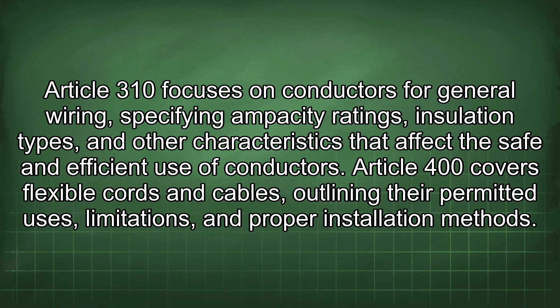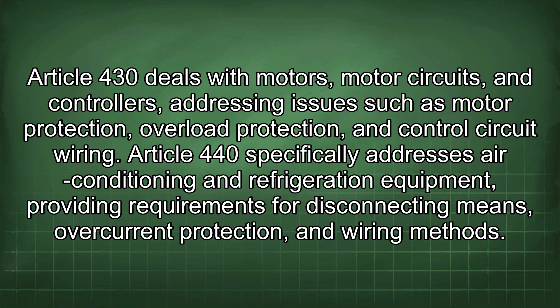Article 400 covers flexible cords and cables, outlining their permitted uses, limitations, and proper installation methods. Article 430 deals with motors, motor circuits, and controllers, addressing issues such as motor protection, overload protection, and control circuit wiring. Article 440 specifically addresses air conditioning and refrigeration equipment, providing requirements for disconnecting means, overcurrent protection, and wiring methods.